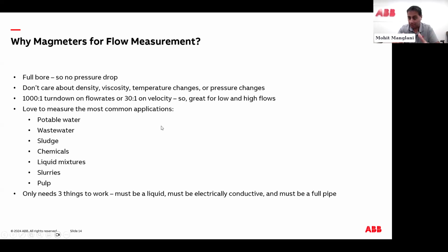In terms of applications, and I'm going to go into more detail on the applications, water is the big application. And even if you have a mix of water with chemicals, slurries, mixtures, pulp, basically anything that's conductive, a mag meter will measure. It's got to be liquid, no gases. Partially filled pipes do not work. It has to be a liquid in that state. It has to be a full pipe. So installation considerations are a requirement, and it has to be conductive because you need to generate that voltage to give you that flow signal. If your conductivity is too low, you might have issues getting that signal back accurately.